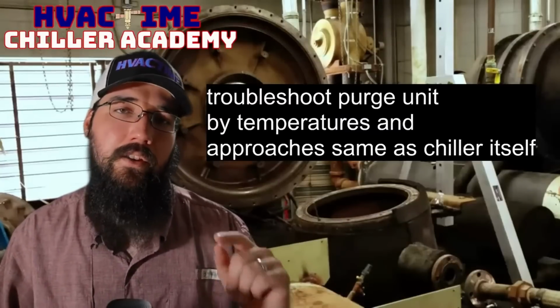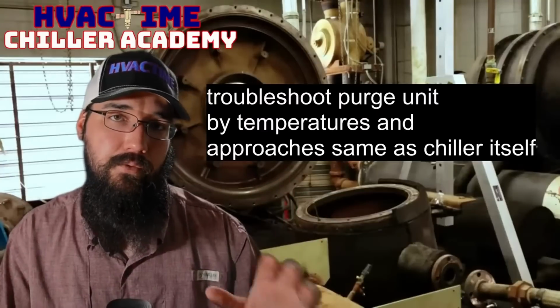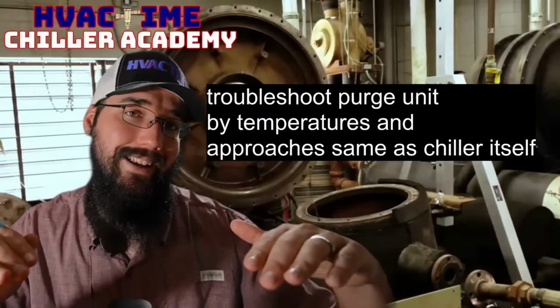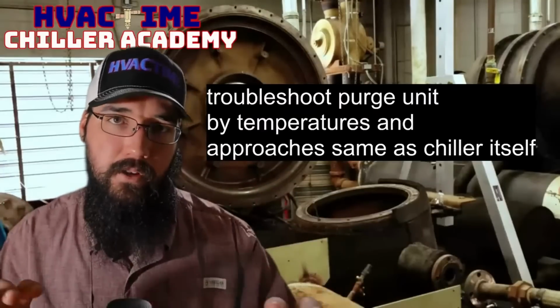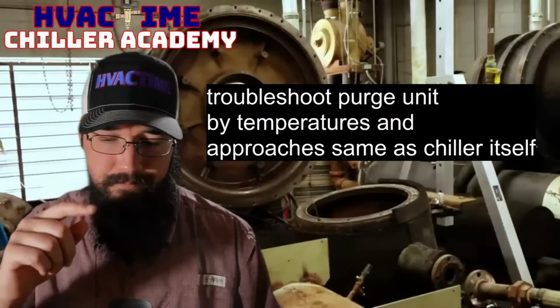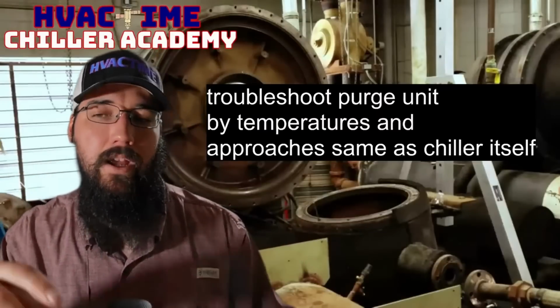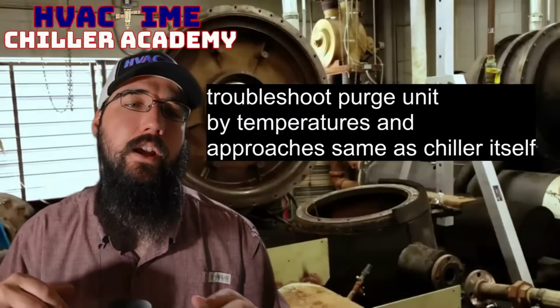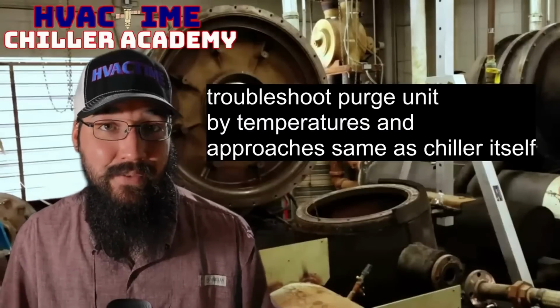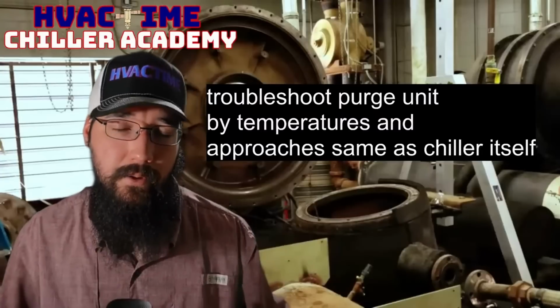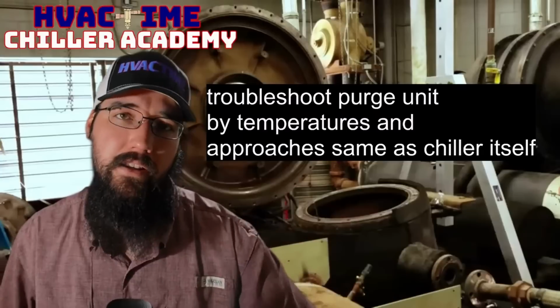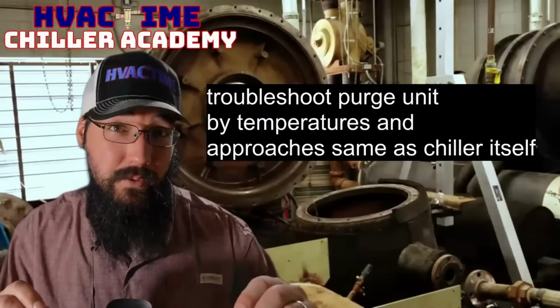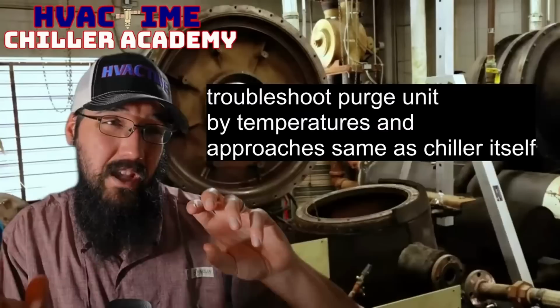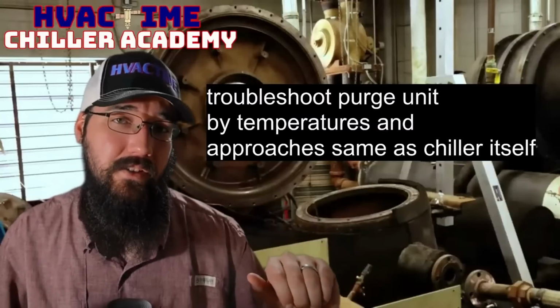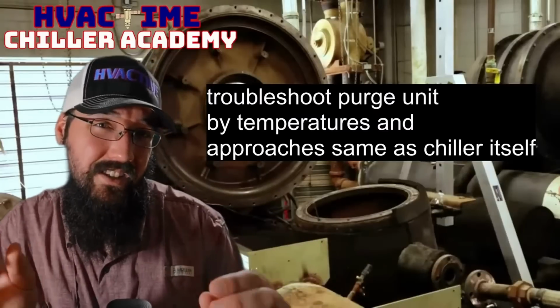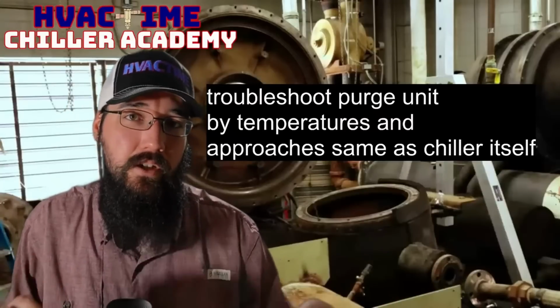If that doesn't show anything, then the next thing I'll do is leave that refrigerant there, add some nitrogen and get that pressure up a little more. Be careful of the pressure ratings, okay? But then I'll do a higher pressure leak search to see if anything comes up that way. If I cannot find a leak, the next thing I'll do is evacuate all that, pull it down, and charge the recommended weight. Usually I'll go maybe an ounce or so extra for me disconnecting. Okay, because I'd much rather have a little bit too much than not quite enough charge in that system.